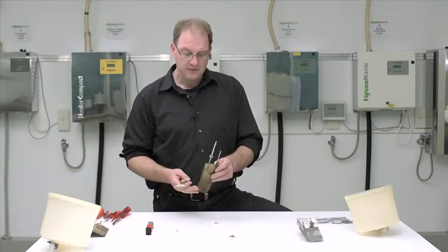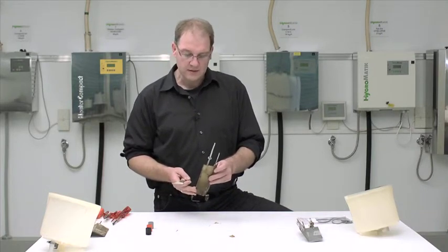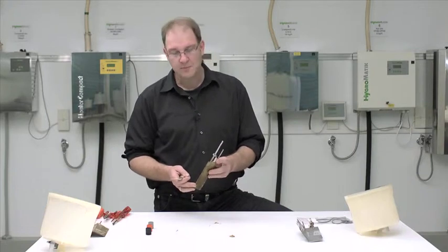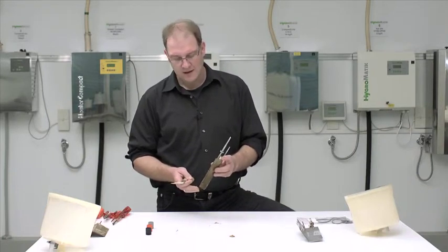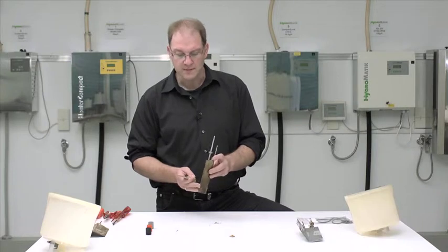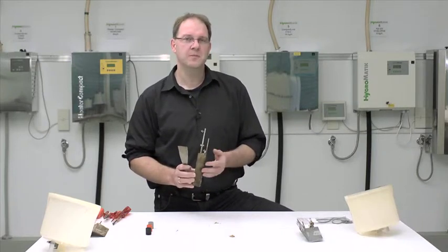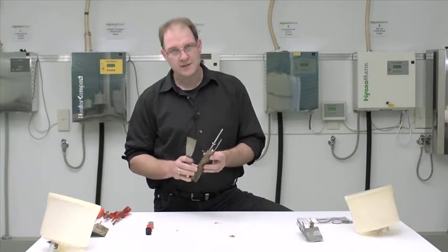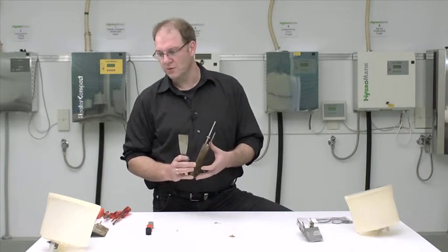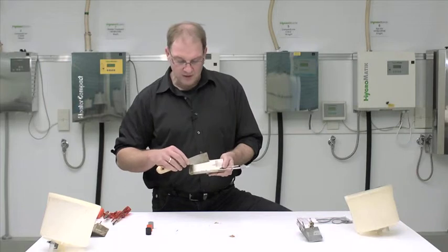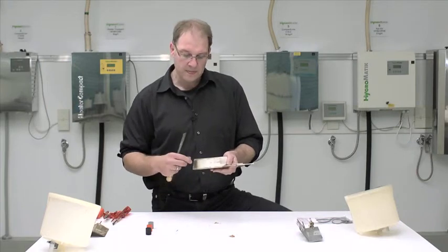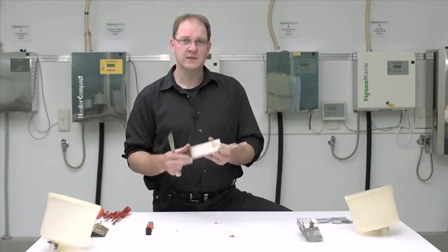Should you on occasion observe that the electrode wear is way too high, then it could be that a certain water parameter, the concentration of chloride in your water, might be too high. We generally recommend switching, if the concentration of chloride is above 50 mg per liter, to galvanized electrodes. And in fact, these electrodes have a zinc-coated surface, and the electrode is thereby considerably more resistant to chloride.